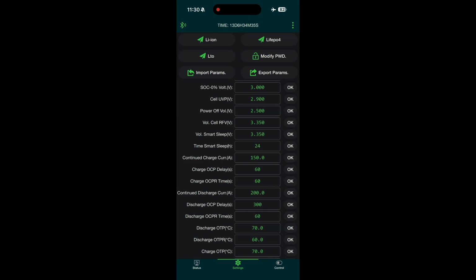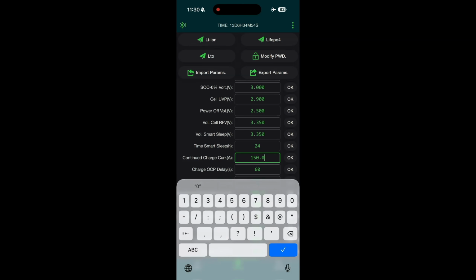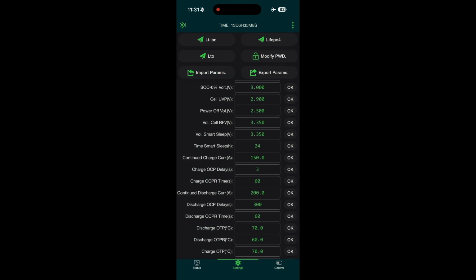Okay, next one is charge OCP delay. So this is the delay for the over current protection. If you found that the charge is coming in, and in this instance it's gone over 150 amps, this is how long you want it to go over 150 amps before the BMS reacts. So I might put that at say 3 seconds, for example. In other words, if it goes over 150 amps, it'll wait for 3 seconds and then it will basically stop allowing charge to go into the bank.